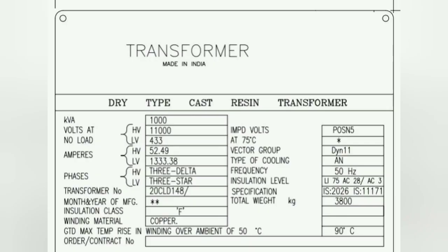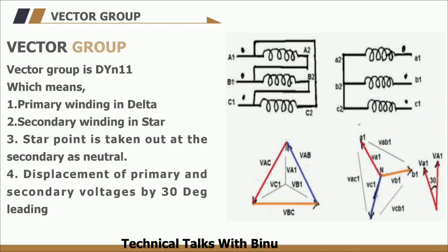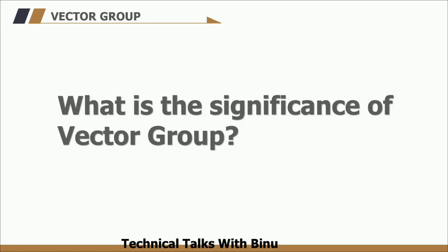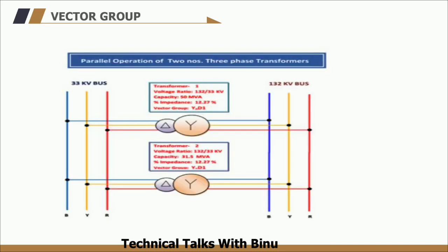Coming back to the nameplate, the next parameter is the vector group, which is Dyn11. 'D' shows delta-connected primary, 'Y' shows star connection in the secondary, 'N' shows that the star point is taken out as neutral, and '11' shows a phase shift of 30 degrees leading between the primary and secondary voltages. The vector group is a method of categorizing HV and LV windings, indicating the winding configuration and phase angle between them. When connecting two transformers in parallel, only transformers with the same vector group should be paralleled — mismatched phase angles will result in circulating currents and system disturbances.